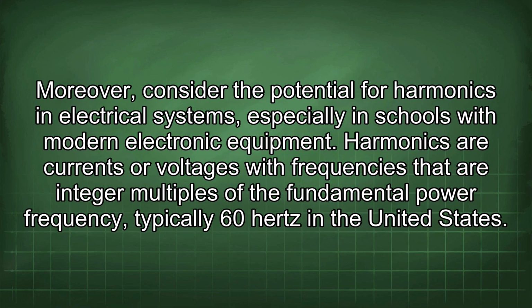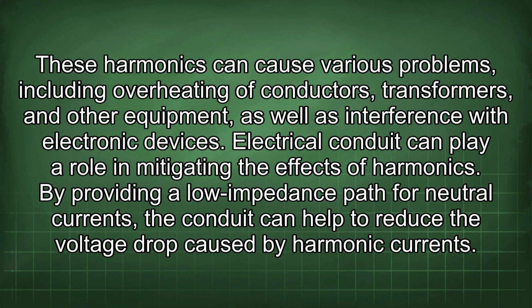Moreover, consider the potential for harmonics in electrical systems, especially in schools with modern electronic equipment. Harmonics are currents or voltages with frequencies that are integer multiples of the fundamental power frequency, typically 60 Hz in the United States. These harmonics can cause various problems, including overheating of conductors, transformers, and other equipment, as well as interference with electronic devices. Electrical conduit can play a role in mitigating the effects of harmonics.